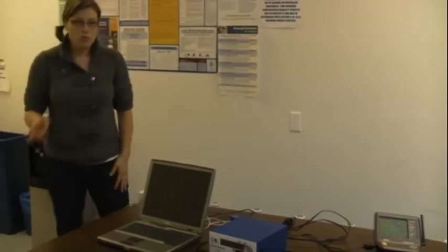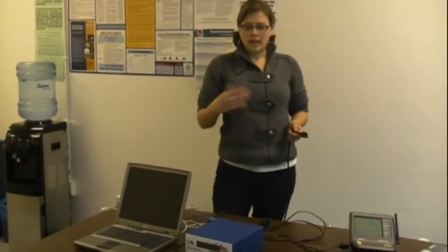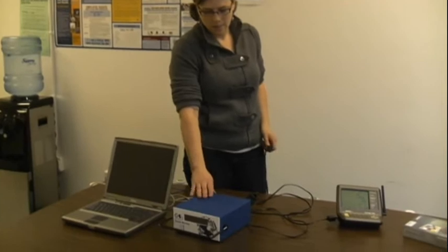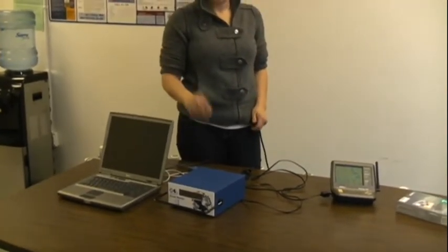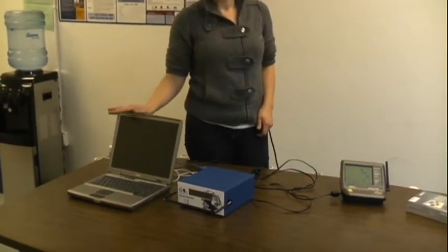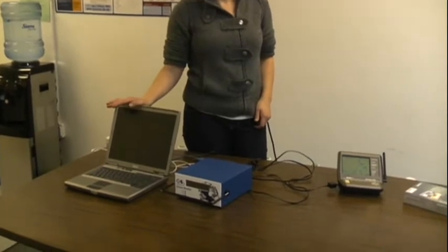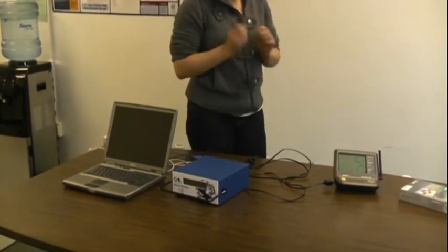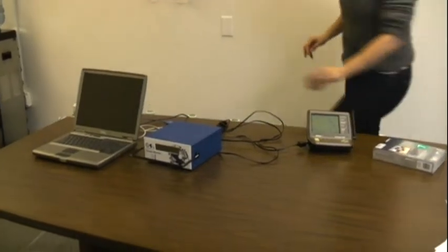The last step we'll show here is how to set the ozone monitor on 10 second averaging. Eventually you'll put it on 15 minute averaging, which means it will upload a data point every 15 minutes. But when you're first getting it set up, you won't want to wait 15 minutes to figure out if it's working or not. So you'll want to put it on 10 second averaging. We'll go ahead and plug in the ozone monitor and turn it on.